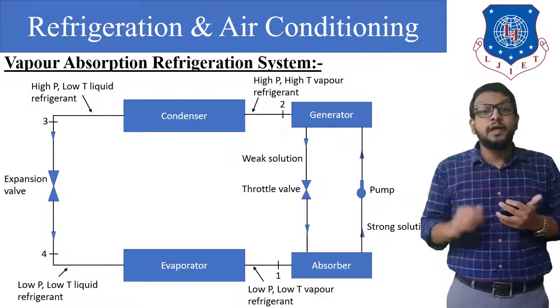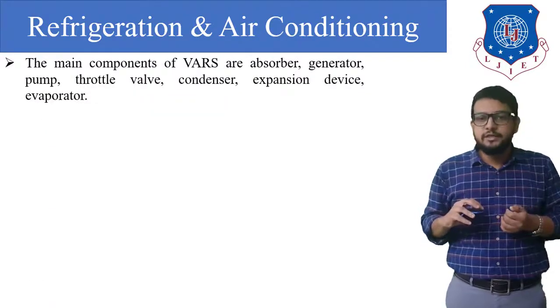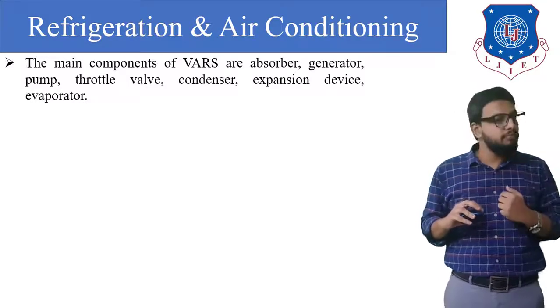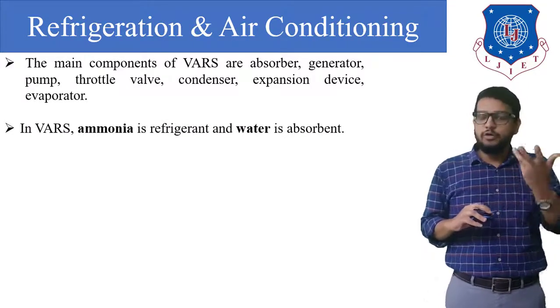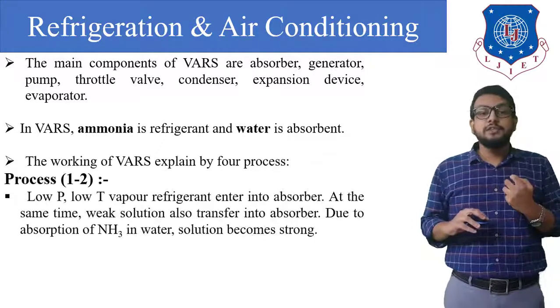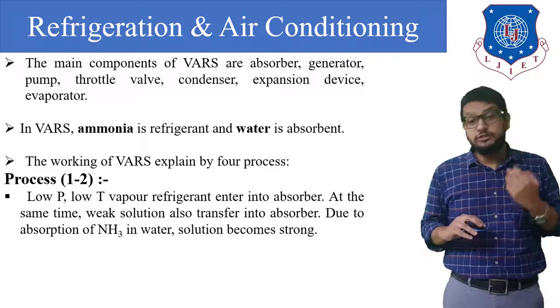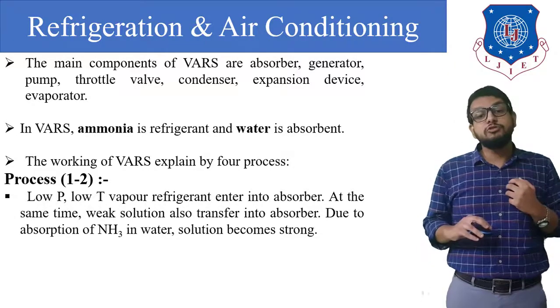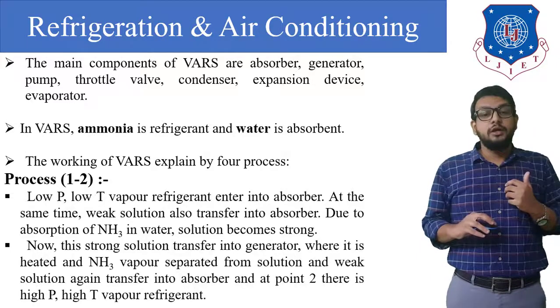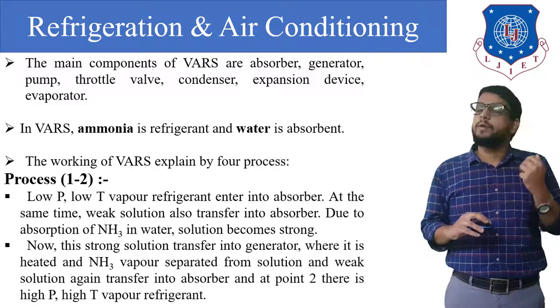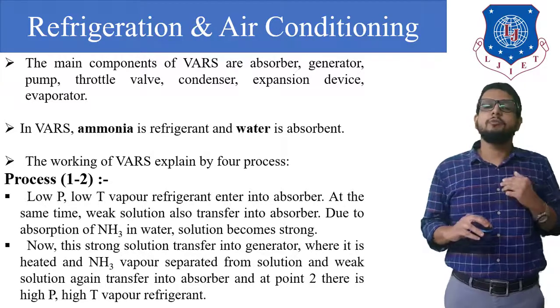The main components of the VAR system are: absorber, generator, pump, throttle valve, condenser, expansion device, and evaporator. Ammonia is the refrigerant and water is the absorbent. In the absorber process (1 to 2), low pressure, low temperature vapor refrigerant enters the absorber; the weak solution also transfers into the absorber and, due to absorption of ammonia in water, the solution becomes strong. That strong solution transfers into the generator where it is heated, ammonia vapor is separated, and the weak solution returns to the absorber.